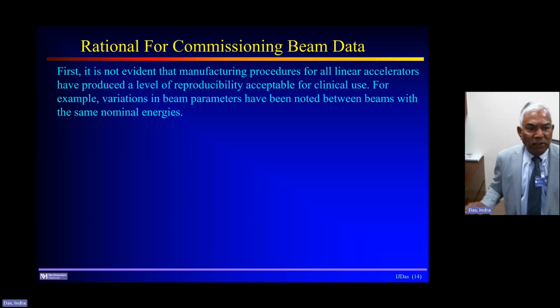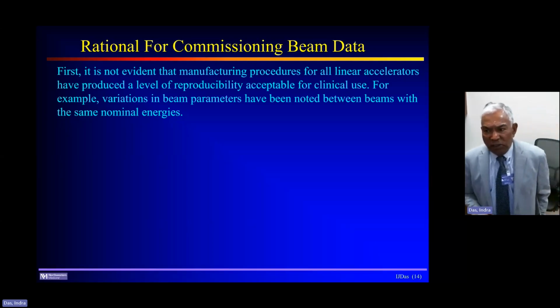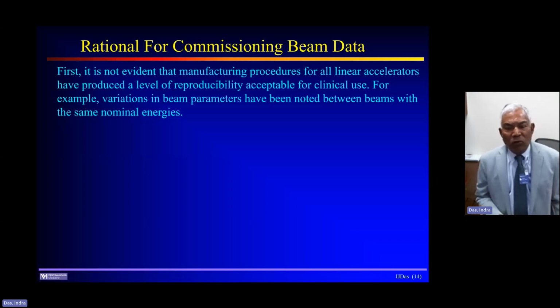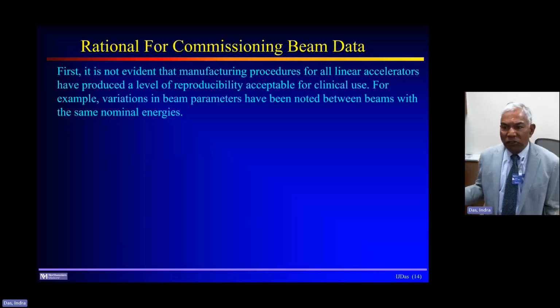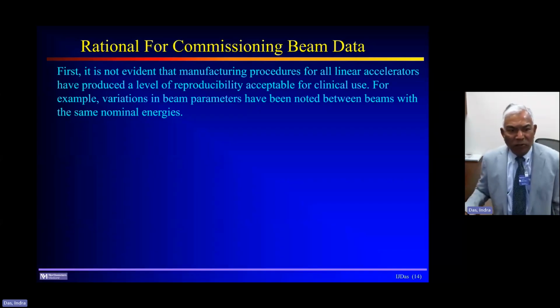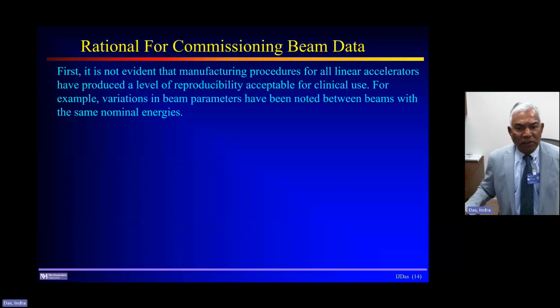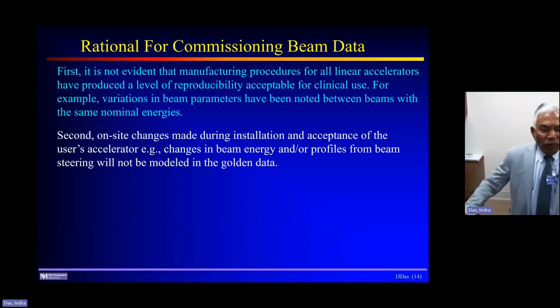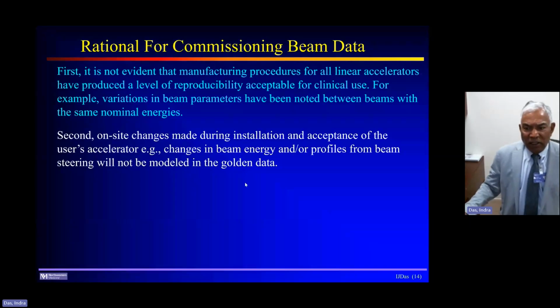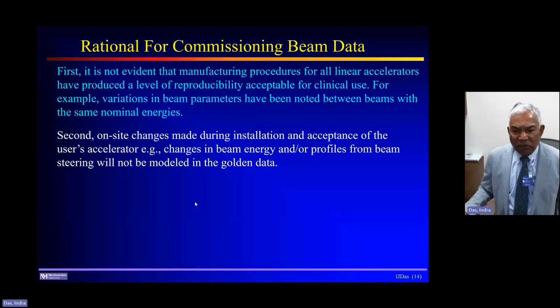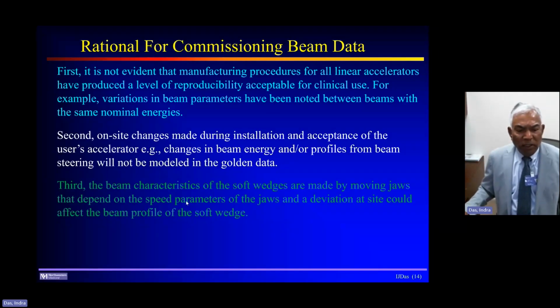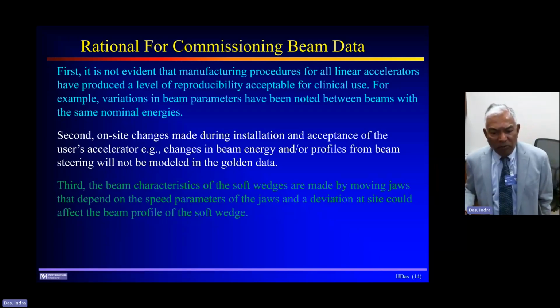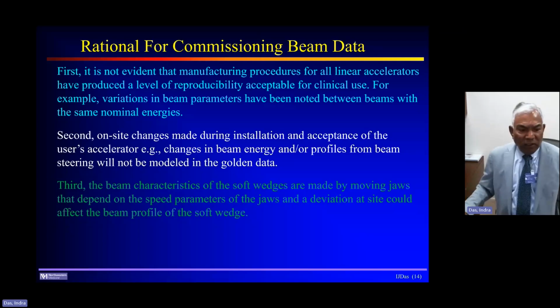Now, the rationale for commissioning data is that the manufacturing process is not robust enough. Like Cobalt 60, it's a monoenergetic beam, so you can just collect the data and be done with it. But that's not true for linear accelerators, and there are changes taking place. Also, when they come and install it on site, there are differences. Your engineer can tweak the beam energies and may create a problem. Third, the beam characteristics of the soft wedges, the enhanced dynamic wedges, are all based on the speed of your jaws, and that can change certain aspects.